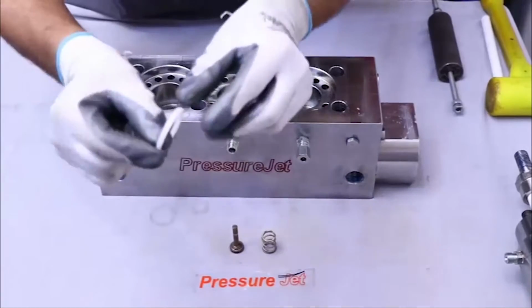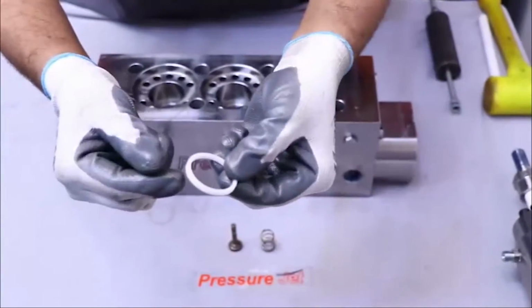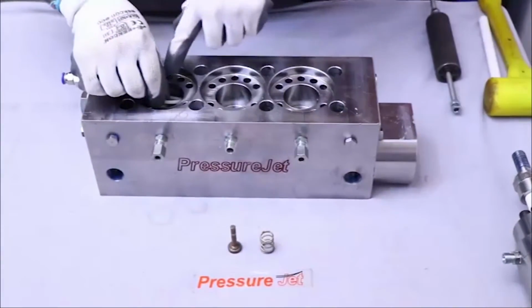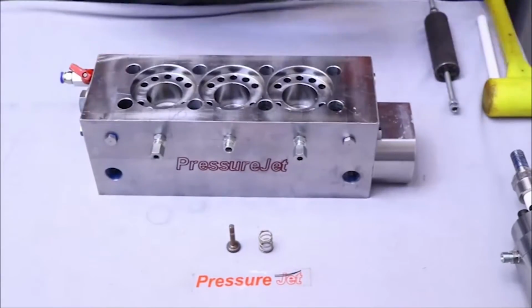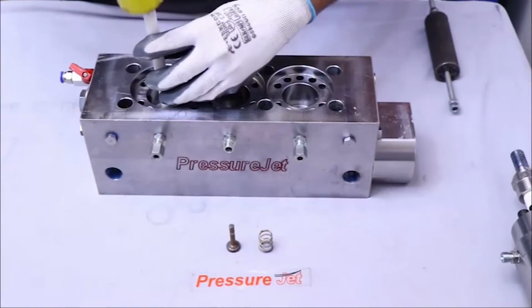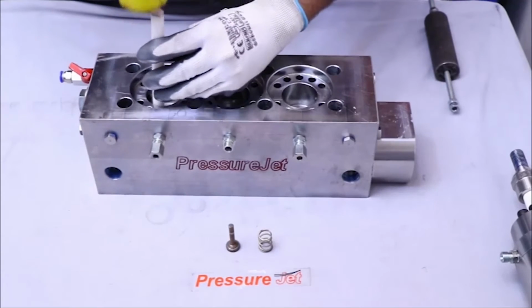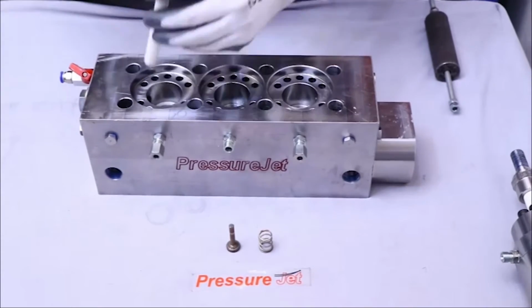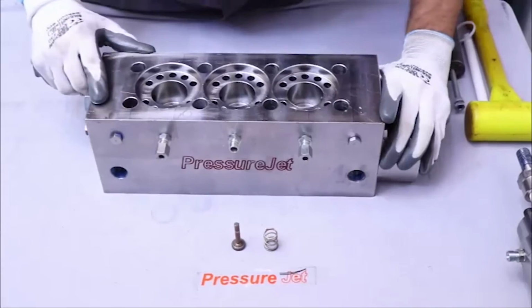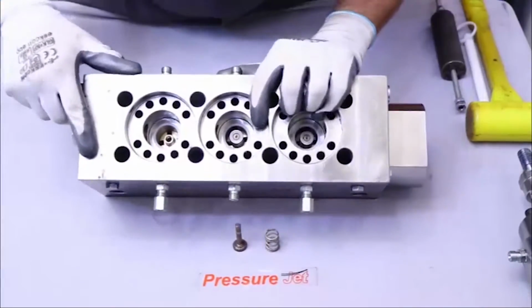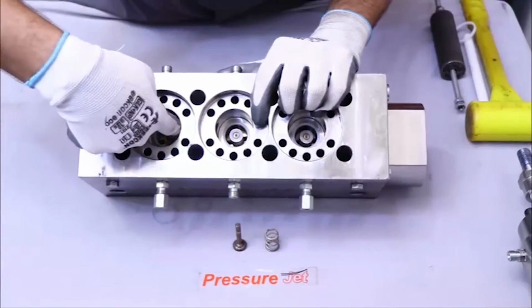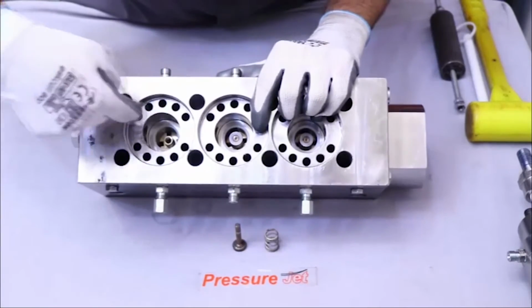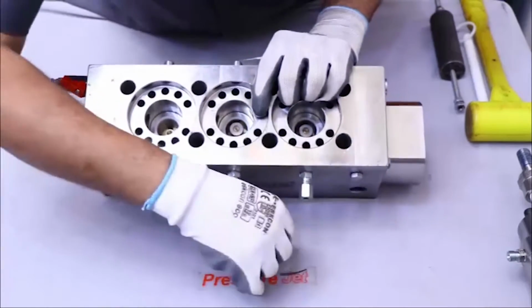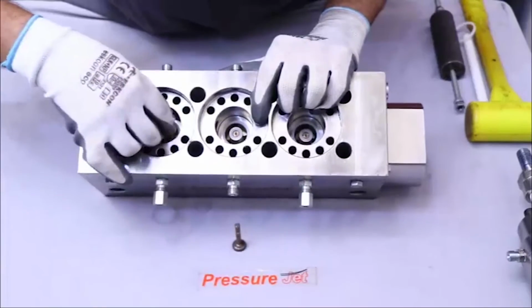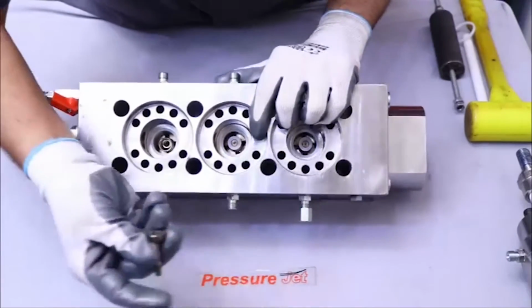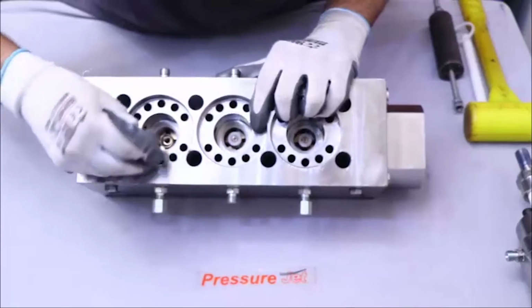After that, take the POM gasket and assemble it. Using a nylon rod and rubber hammer, fix it in its position. Then assemble the helical spring and discharge valve. Firstly, take a helical spring and put it in, and then install the discharge valve.